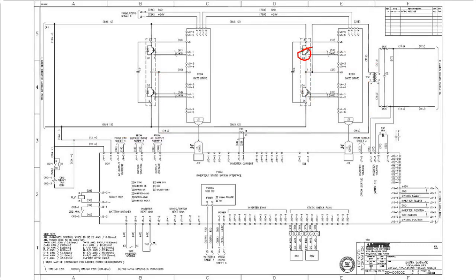And then when we switch this IGBT set on, if you follow the positive through, and I can't draw to the top there because there's something in my way, basically power comes down here through that, and then goes back up this transformer to here. So this becomes positive there, and then the negative goes down through this IGBT back that way. So that's negative. This way we get the negative going pulses. If you took an oscilloscope and went on this transformer here, what you would actually see, and this is a very crude, rudimentary version because it's actually at 8 kilohertz that we do this, it would look like that. There's your zero line there, okay? But coming out of here, because of the inductance in the transformer and the capacitor, we will have beautiful AC coming out here to your load circuits.